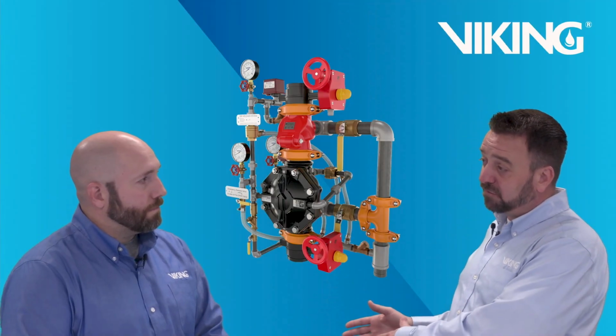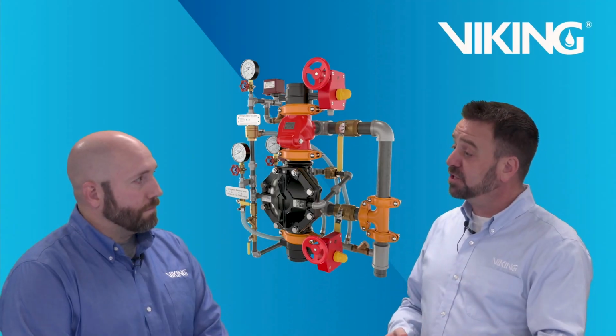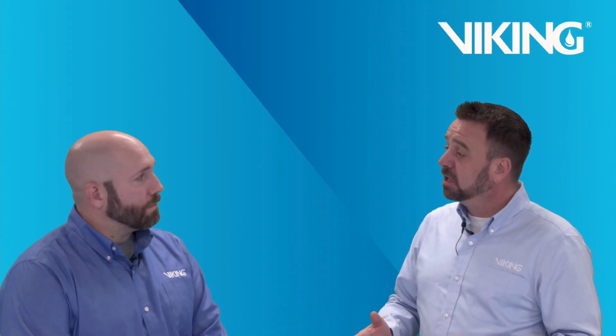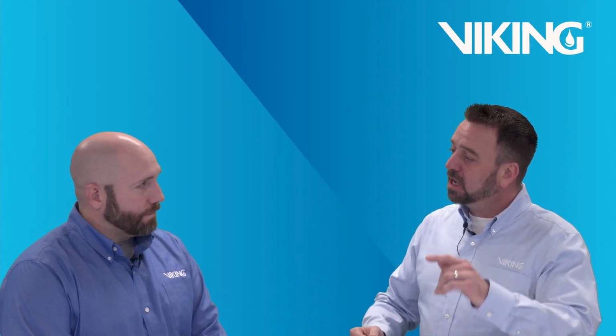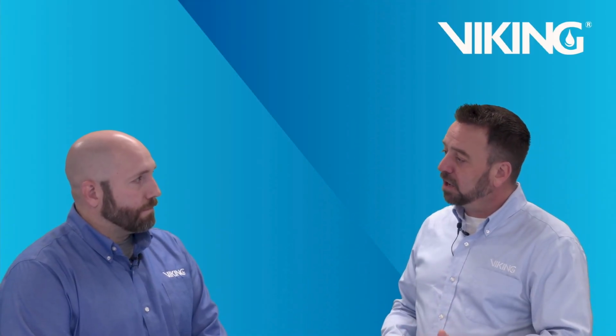So with the dry to pre-action upgradable, that's one method for doing it. Another one would be the Total Pack 4 system. Okay. Total Pack 4 system will be our cabinet system. And with the Total Pack 4, it's actually even easier than the dry to pre-action upgradable system, because to upgrade from a dry to a pre-action system, all you got to do is change a couple dip switches within the cabinet and you just made the upgrade.